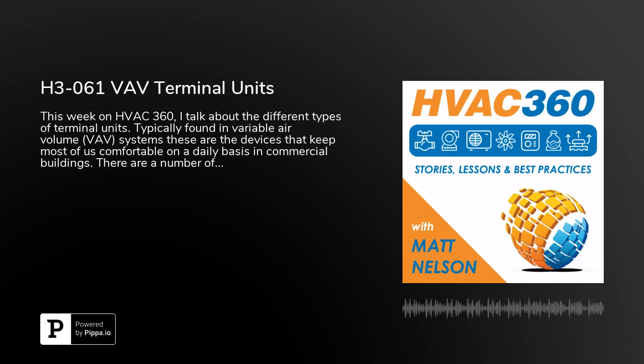You have a parallel fan-powered box, and that fan actually pulls air directly from the plenum. And so you can take that constant plenum air, and sometimes that fan's on, sometimes it's off, sometimes the primary air valve is opened all the way. But it basically has two inlets, and one of those inlets has the fan on it.